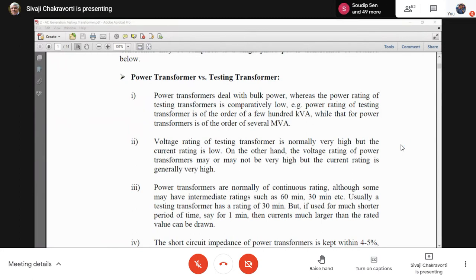On the other hand, there is the testing transformer which I have shown. Now this is only testing the equipment. But when I say testing the equipment, which one is it testing? Is it testing the conductors? Is it testing the magnetic materials, or is it testing the insulation? Which one is it testing? What do you feel? Insulating material. Insulating material, correct. Now, insulating materials are not conductors. They are bad conductors of electricity. So therefore, the current will be very low. For example, the two transformers that I have shown, although together they can go up to 1500 kV, their current rating is actually very small. It is even less than 1 ampere because that current is not required there.